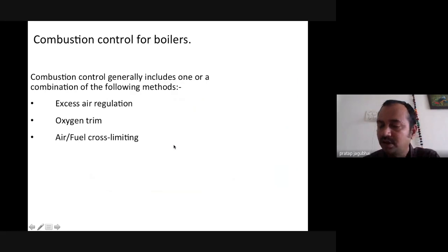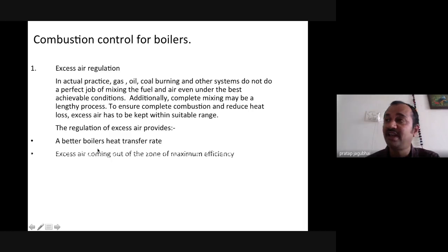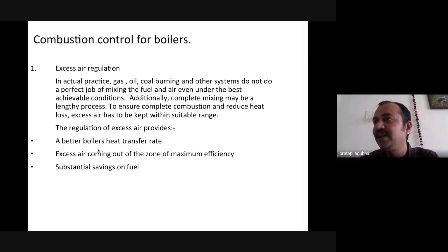So how do we optimize further on that? After all this control philosophy is available within the necessity and permissions in our boiler house, we can optimize all these things together for the result we require from the combustion controls. Combustion control is basically the excess air control or O2 trimming, as well as the air to fuel regulation based on pressure. I will come to these one by one. The excess air regulation, as I said, is the control to optimize the heat loss.